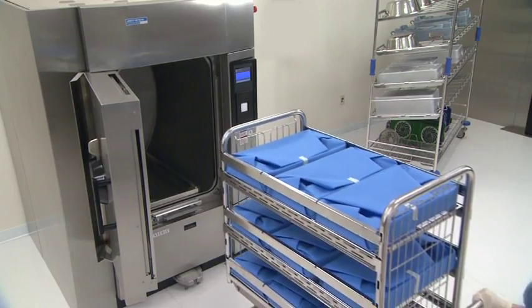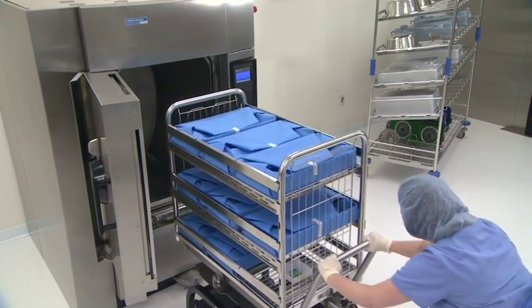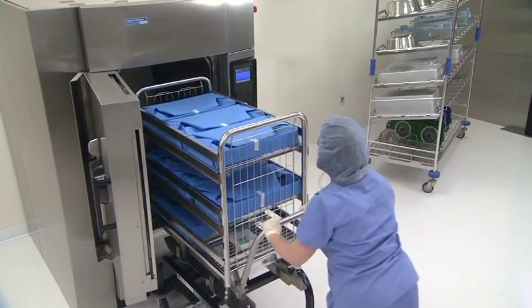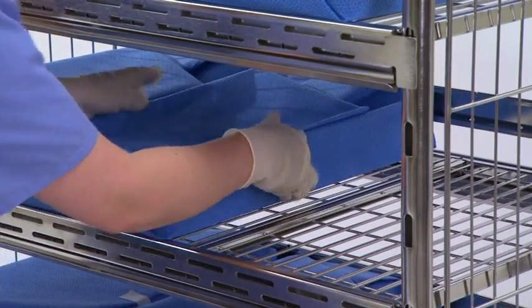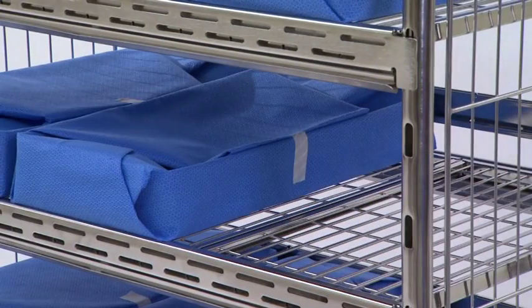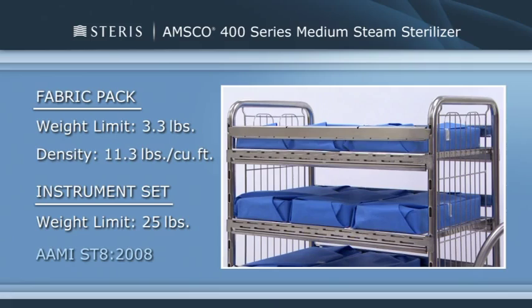The AMSCO 400 series medium steam sterilizer holds commonly used wrapped or unwrapped instruments and equipment. Wrappers must be made of 100% cotton, 140 thread count 2-ply fabric, and must be laundered. It also handles non-woven disposable wrappers. Limit the weight of each fabric pack to approximately 3.3 pounds and density to 11.3 pounds per cubic foot. This ensures complete steam penetration and minimizes moisture retention. Specific guidelines can be found in AAMI ST8 2008. Limit the weight of each wrapped instrument set to 25 pounds to minimize moisture retention.